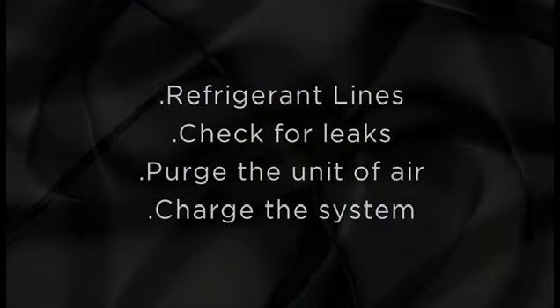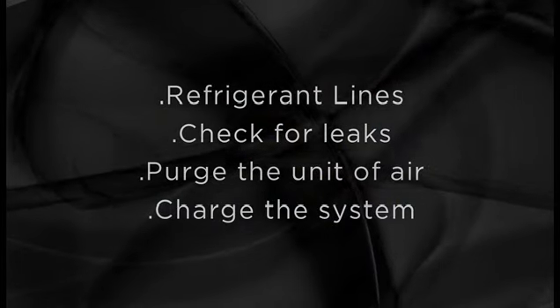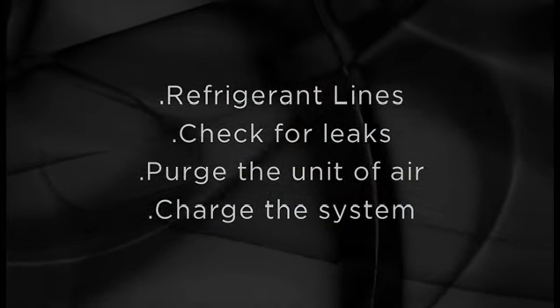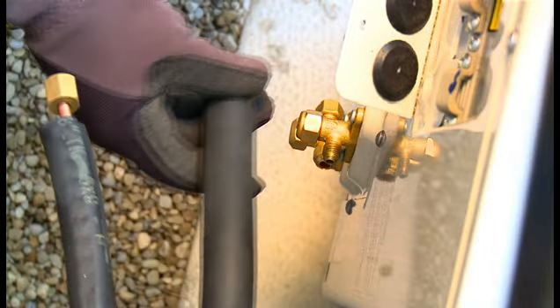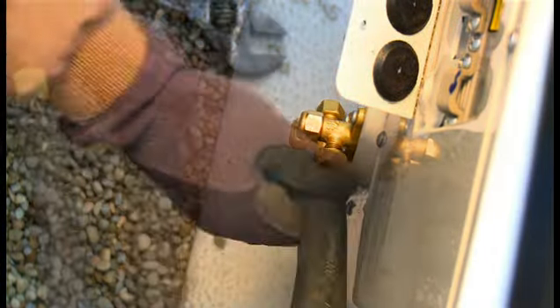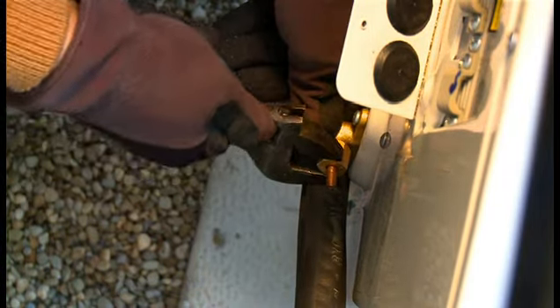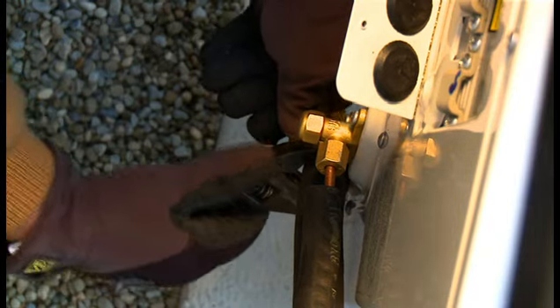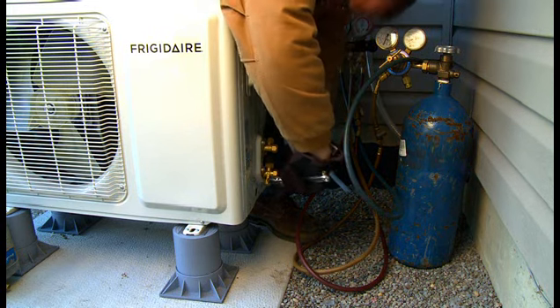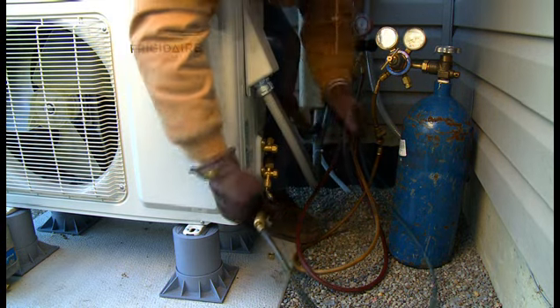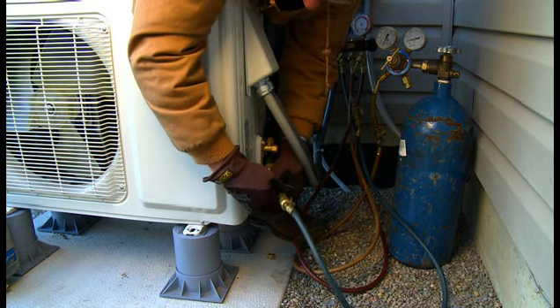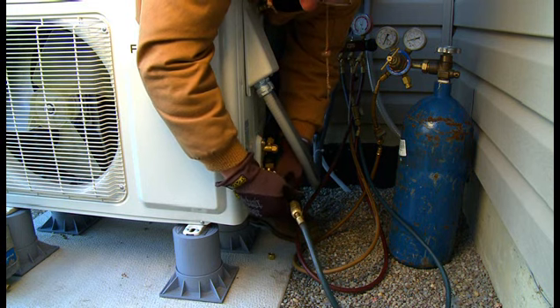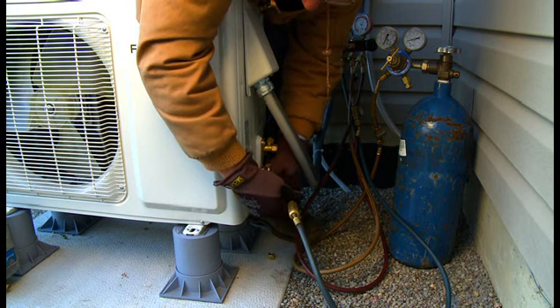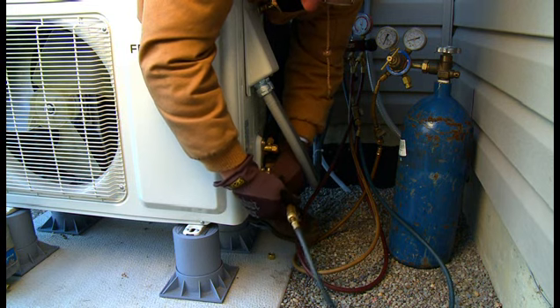We will now connect the two refrigerant lines to the exterior unit, check for leaks, purge the unit of air, and charge the system. Before completing the connections, if necessary, flare the copper lines. Connect the lines to the exterior unit. Using an adjustable wrench, tighten the connections. In these next steps, we'll use nitrogen to check the lines for leaks. On some models, including the 12,000 BTU unit, rather than a 1/4 inch connection, a 5/16 inch connection is used. These models require an adapter.